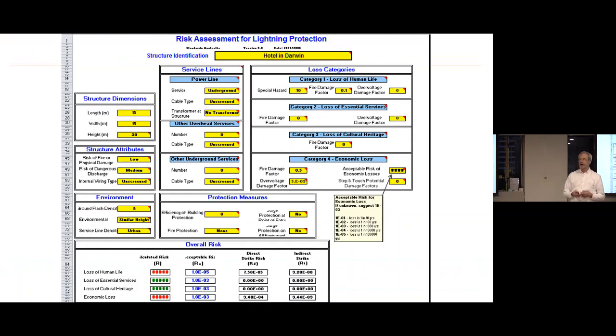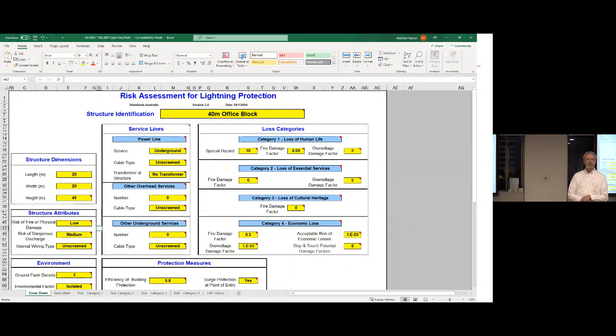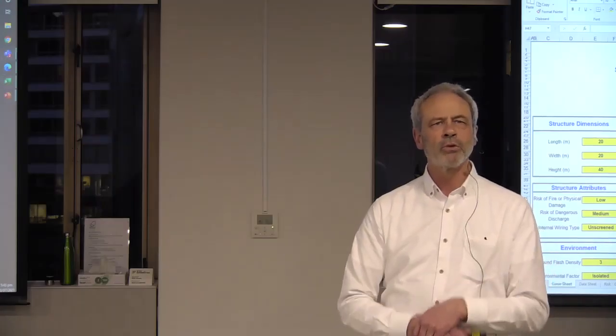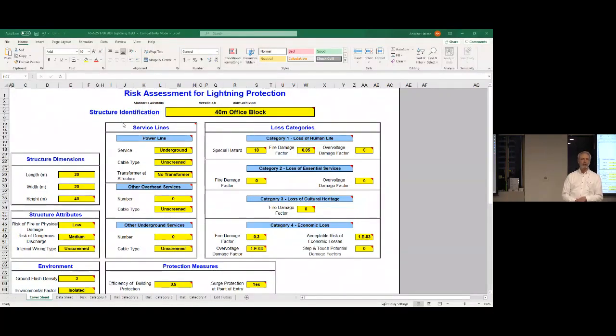This is the risk assessment calculator out of the Australian New Zealand Lightning Protection Standard AS/NZS 1768/2007. It's an Excel spreadsheet that comes with the standard. And so Holly's going to help me here a little bit by bringing up an actual spreadsheet for a moment. Right, not the same spreadsheet, but you'll see there's yellow cells there. The blue titles there on the left are structure dimensions, structure attributes and environment. So we have to enter in the factors that are applicable to that particular structure.